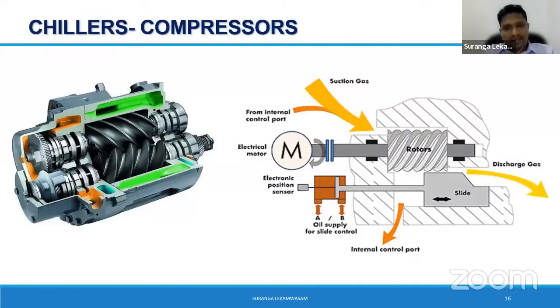So if you choose to go for a VFD, your initial cost may be high. Again, when you have a bigger VFD drive, that adds a lot of harmonics to the system. You may have to go for a harmonic filter itself. So things are complex if you only concentrate on VFD loading and unloading. Therefore there is another option. For screw chillers, you can go for stepless control. That means loading and unloading continuously within the range from 100 to maybe 20% with the use of slide valves. Many of the non-VFD chillers work on the slide valve principle, right? Movement of the slide valve changes the compression ratio so that you get different refrigerant flow through the compressor.